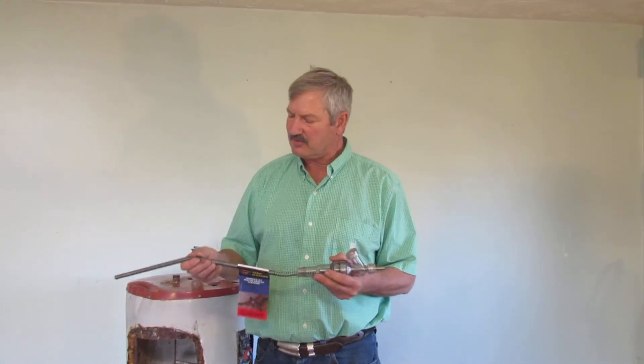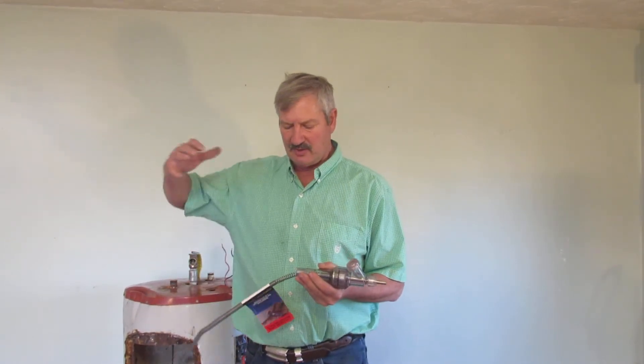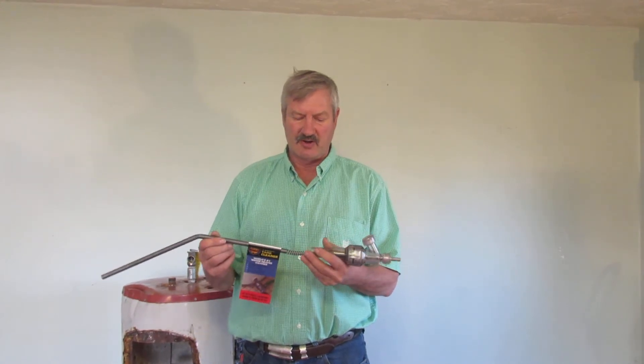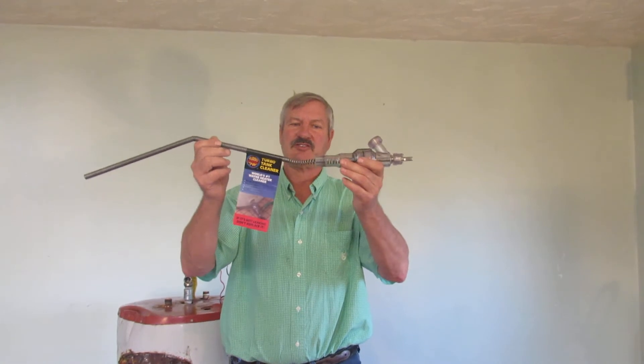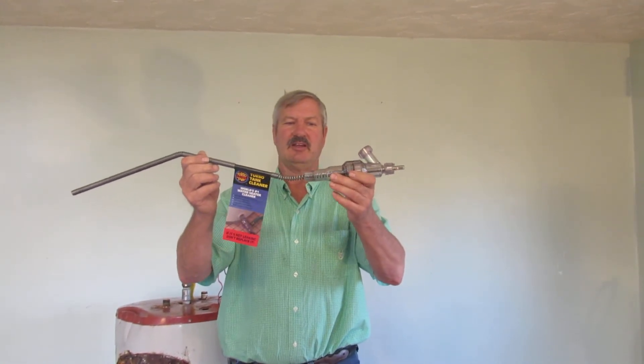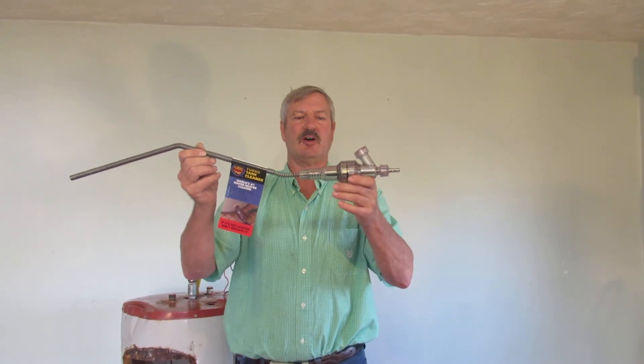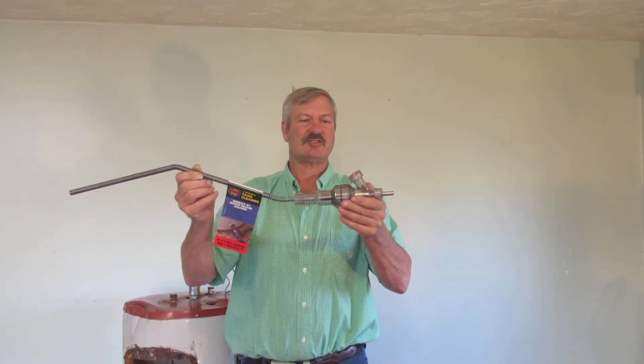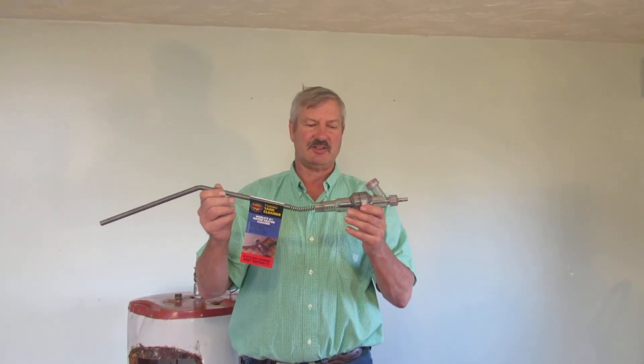This agitator is going to flop around inside your tank and stir up the sediment. The flow of water will sweep it right to the mouth of the tool where it is met by an auger. The auger will pull it inside, bust it up, and prevent plugging. Once inside, the sediment is ground up in the grinding chamber along with the water to form a fine slurry that is discharged out through the garden hose to a remote disposal location.